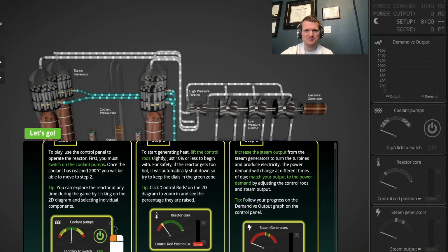Okay, this is something you would never do in real life. Nuclear plants have right-of-way. Certainly within the US, and I can't imagine the UK doing anything differently. And there's a reason for that. And the reason for that is xenon is produced, which effectively acts as another set of control rods. Now, it can build in and burn out over time. What you need to know for reactor operations is you like having xenon at an equilibrium concentration because that makes it easier to maintain reactor power at 100%, or if you're doing a hold for 50%, and so on.